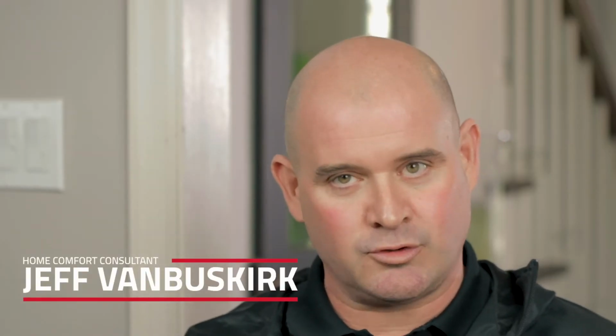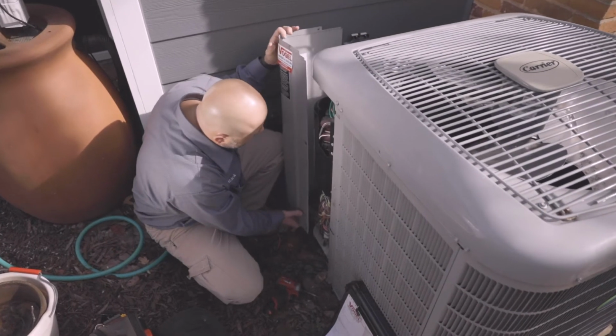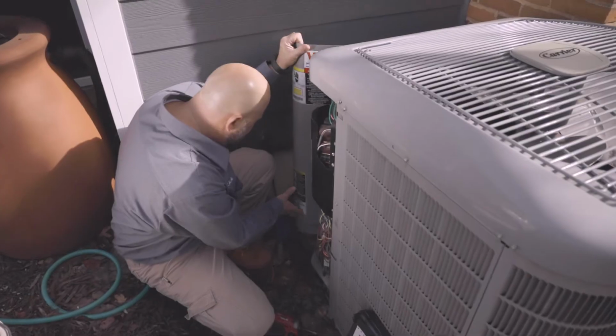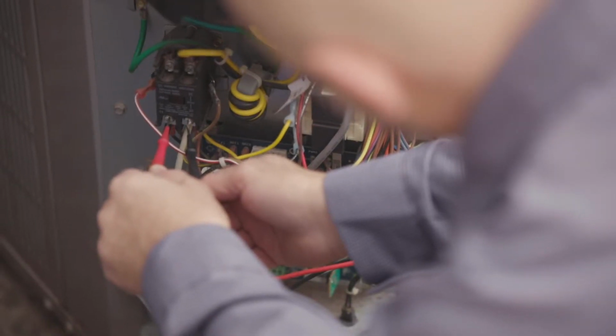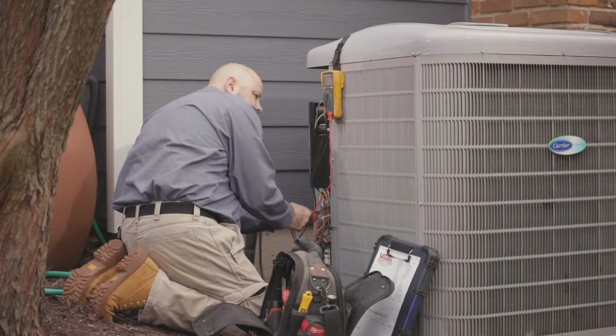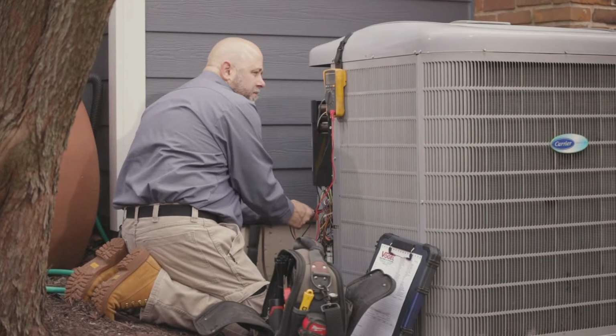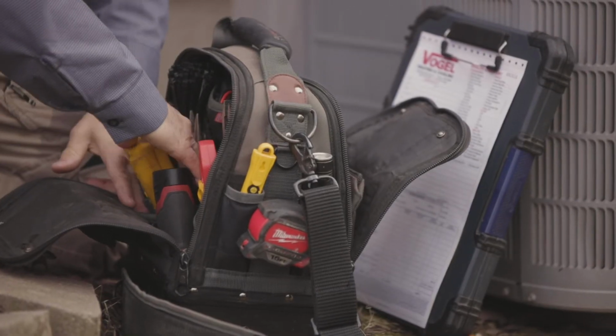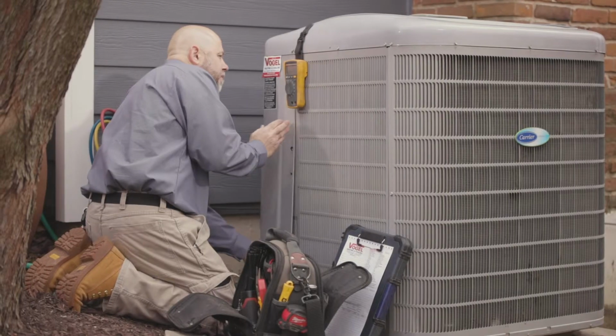But with an air conditioner, you have to have it sized perfectly. Everybody thinks, oh, bigger is better, let's get a big, strong one. That's not so in air conditioning, because if it's too big, it kicks on, it cools the house really quickly, and it shuts off really quickly. You want it properly sized so that it gets a proper run time. If it's bigger, you're going to get a lot of short cycling where it kicks on and turns off a lot. A lot of energy is used at startup.